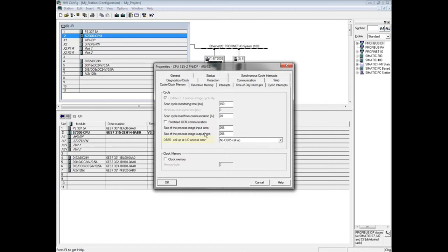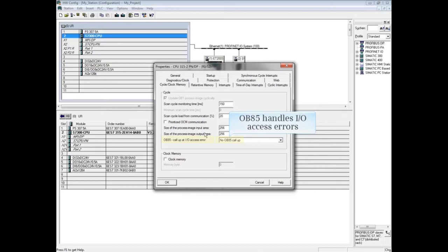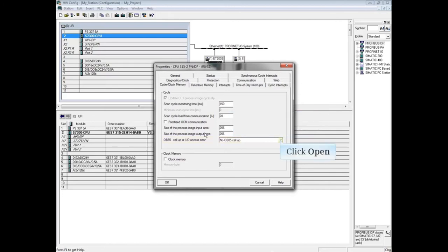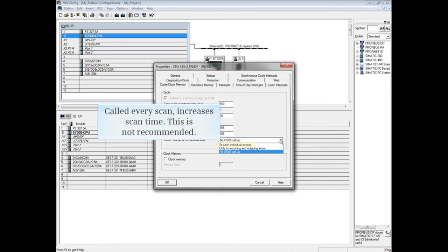The default for OB85 call-up at I/O access error is no OB85 call-up. The optional organization block 85 can be programmed and downloaded for a response if an I/O access error occurs during the update of the input or output process image. If you wish to program an OB85 call, it is recommended that you not choose 'at each individual access' or OB85 will be called every scan.